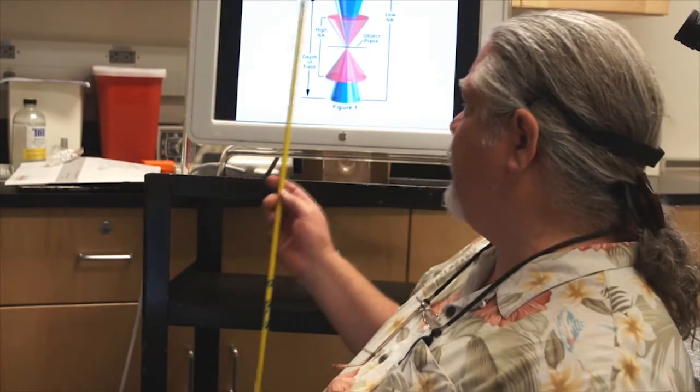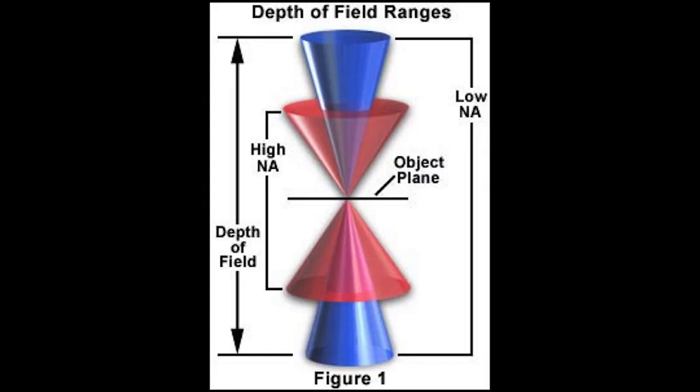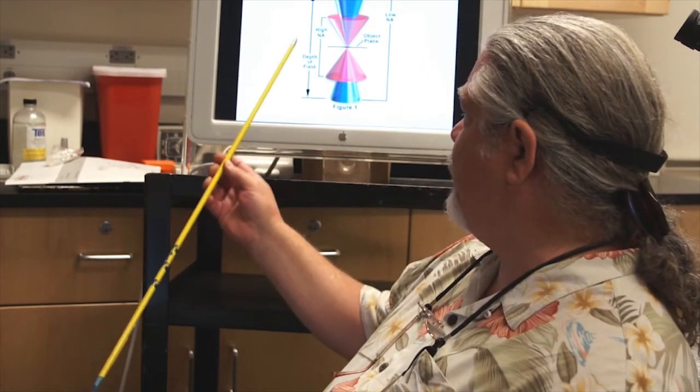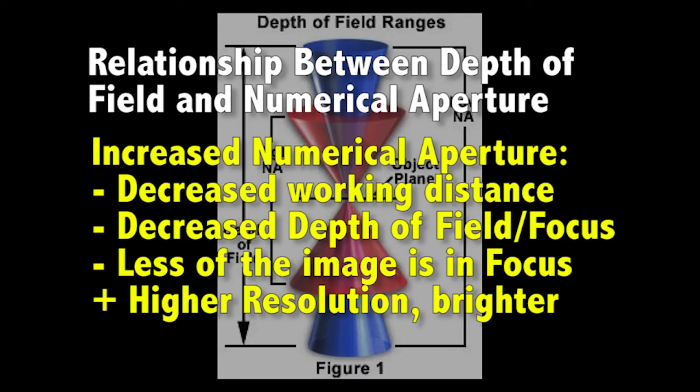Here I have a diagram that shows a low numerical aperture objective with a very large depth of focus. Everything from the top of this blue cone to the bottom is in focus with a low numerical aperture objective. That means a lot of information is traveling through the objective, so it's not highly resolved. When you increase your numerical aperture, not only do you decrease your working distance as we saw before, but also your depth of field or depth of focus decreases. Less of the image is in focus at one time, but it's at a higher resolution and it's a brighter image.